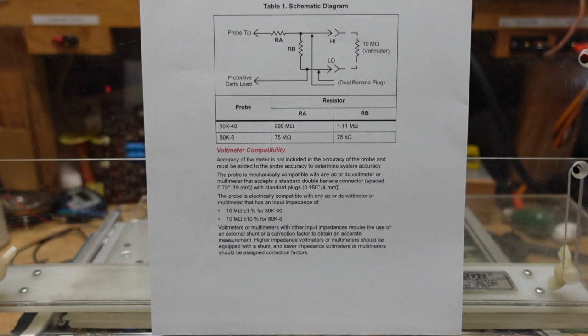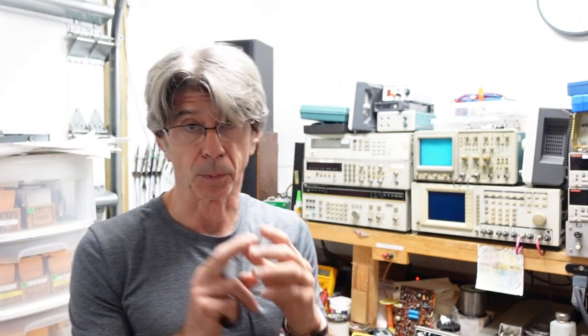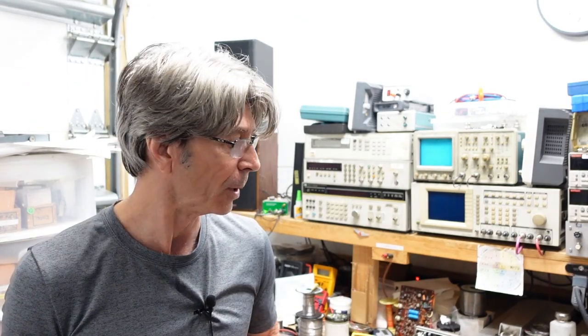There are many Tektronix 465 still in service today, which is a testament to superior design, construction, and parts used. That said, they are now around 50 years old and they're going to have problems because nothing lasts forever. So we have a no display problem. What can cause that? The vast majority of times it's usually an issue with the high voltage supply that feeds the CRT. There are other things that can cause it: you can have blanking issues, you can have other low power supply issues.